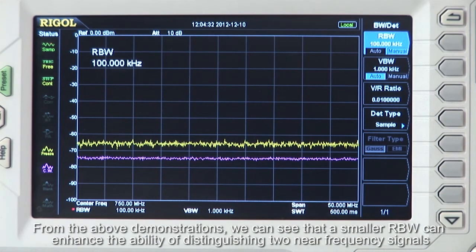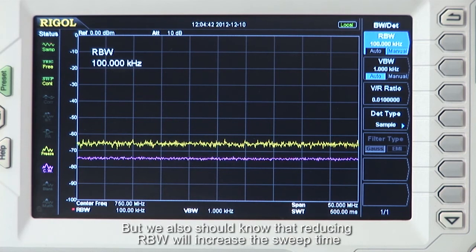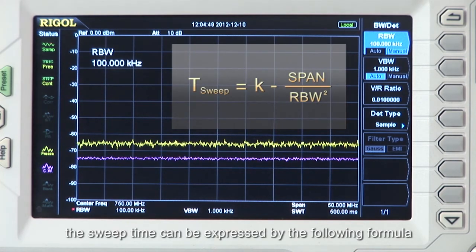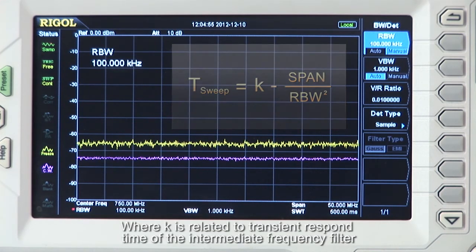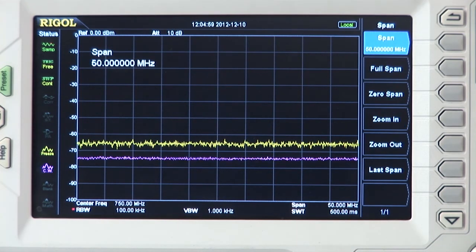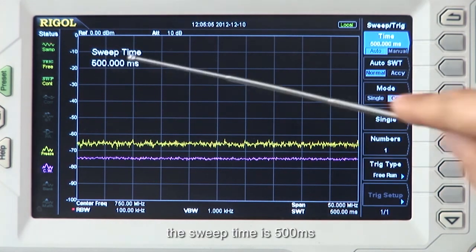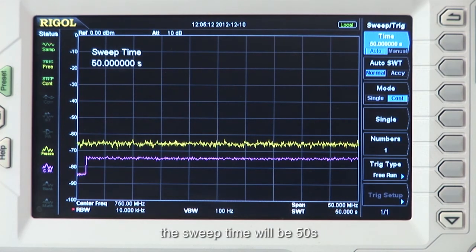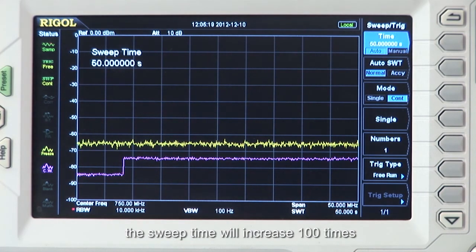From the above demonstration we can see that a smaller RBW can enhance the ability of distinguishing two frequencies that are near one another. It also reduces the DANL, but we should also know that reducing RBW will increase the sweep time. When the RBW is smaller than the video bandwidth, or VBW, the sweep time can be expressed by the following formula, where K is related to the transient response time of the intermediate frequency filter. When we set the span to 50 MHz and the RBW to 100 kHz, the sweep time is 500 ms. But when we set the RBW to 10 kHz, the sweep time will be 50 seconds. This means that when the RBW is reduced by 10 times, the sweep time will increase 100 times.